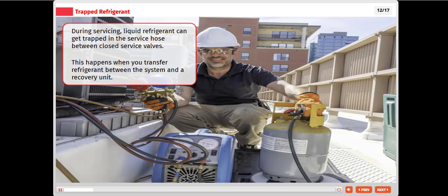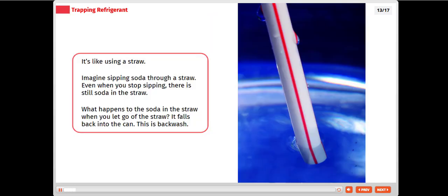During servicing, liquid refrigerant can get trapped in the service hose between closed service valves. This happens when you transfer refrigerant between the system and a recovery unit. It's like using a straw. Imagine sipping soda through a straw. Even when you stop sipping, there is still soda in the straw. What happens to the soda in the straw when you let go of the straw? It falls back into the can. This is backwash.